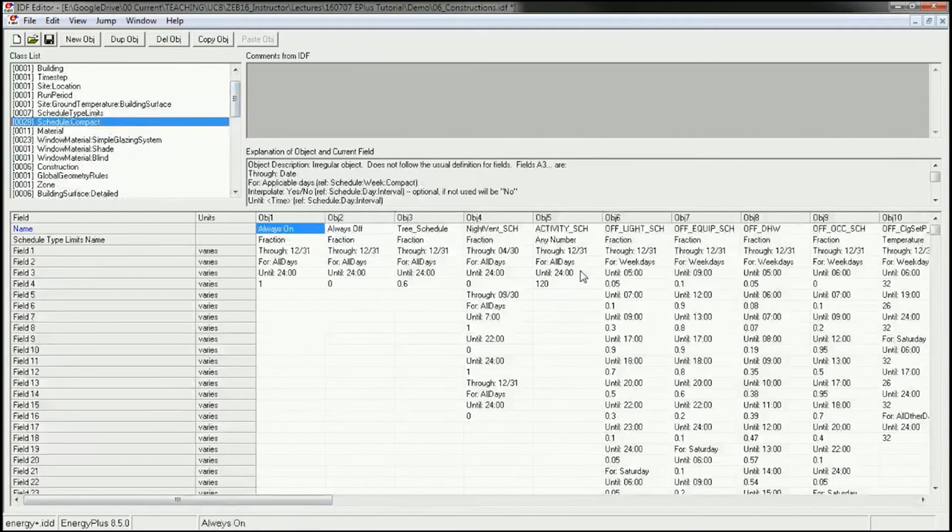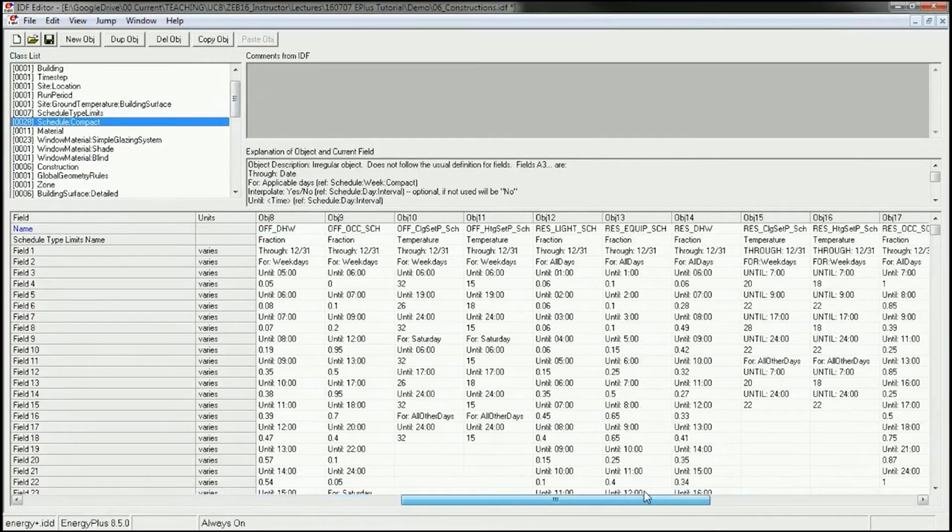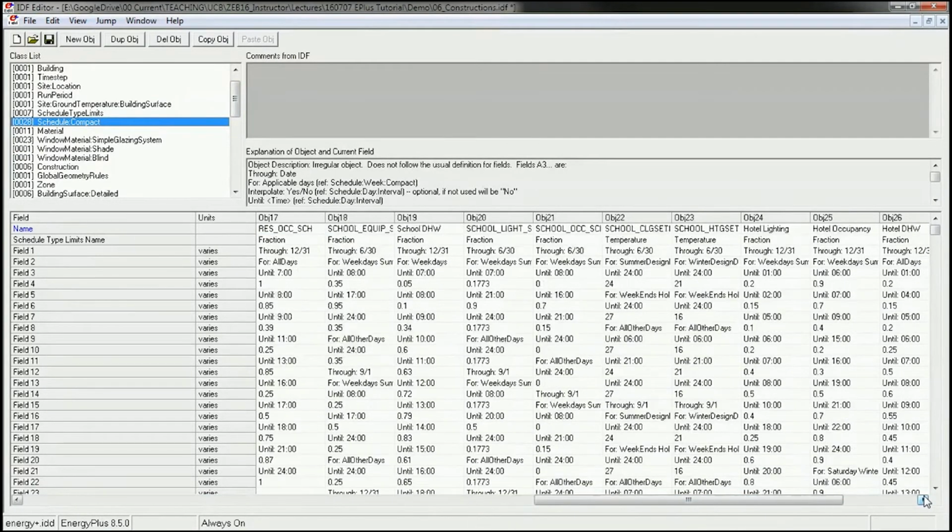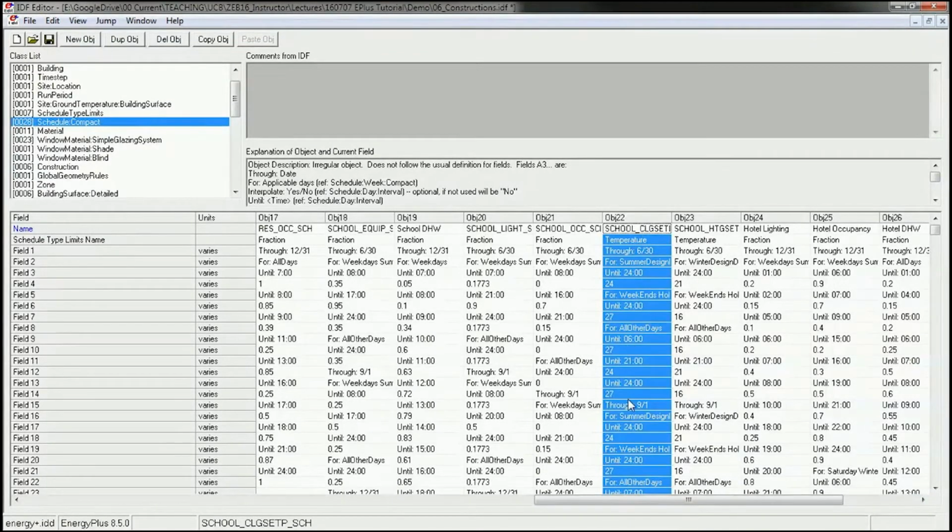So going back to my school thermostat here, I was trying to make a point about the cooling system. In Worcester, there is no cooling system, and so to simulate that, we have a choice. We can simulate the energy use as a proxy for comfort, or we can simulate the energy use that is likely to occur in the actual system. If you want to use the thermostat settings as a proxy for comfort, you should leave them at reasonable levels that you think are appropriate for comfort. If you want to simulate the actual energy use of the HVAC system, regardless of comfort, you can change the thermostat settings to make sure that either the heating system or the cooling system never goes on, and they will affect how you should interpret those results.